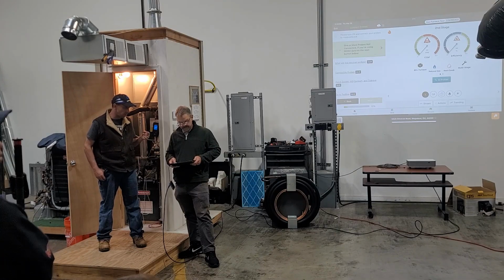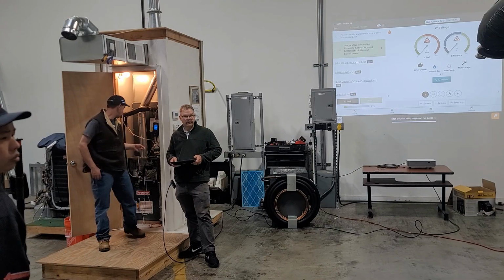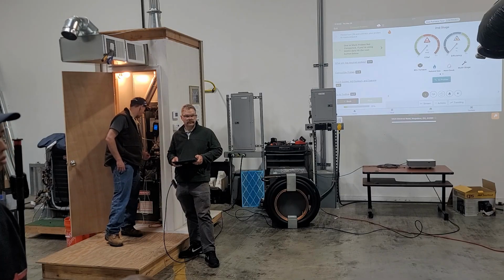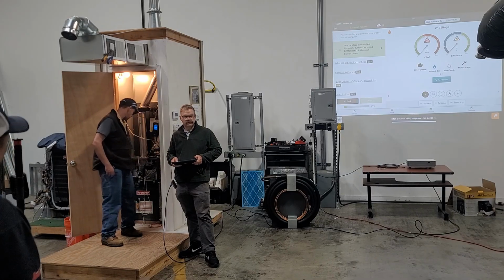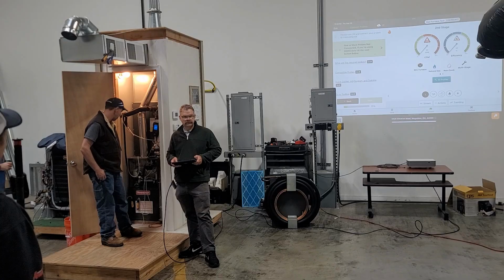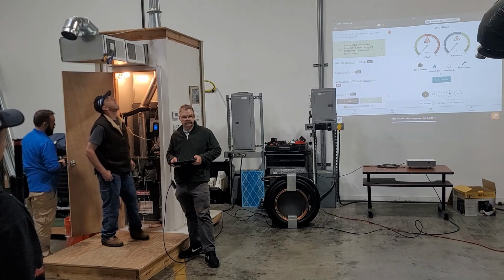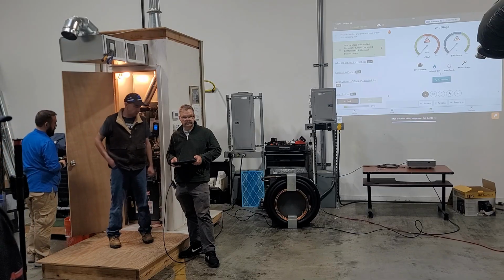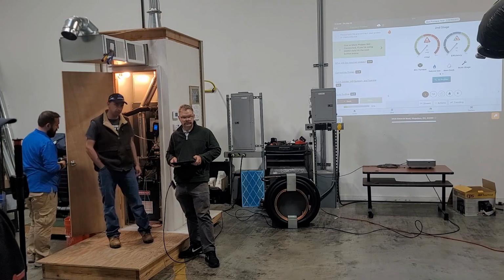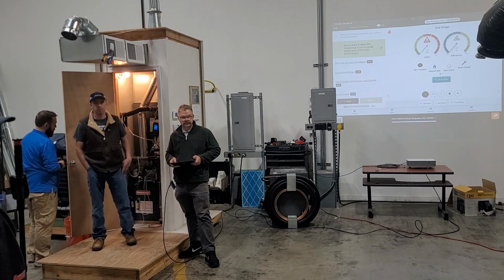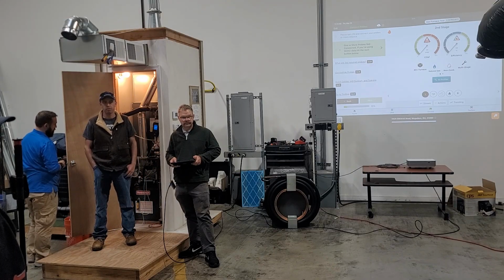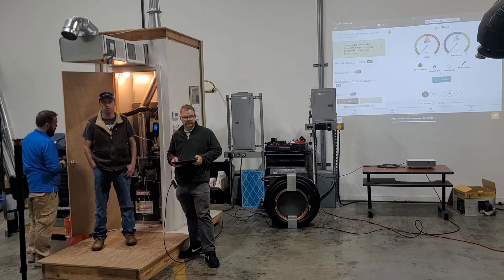For those of you who haven't done the gas workflow, I'd highly suggest it. I keep the Fieldpiece gauges, and I also have the Testo manometer, the dual manometer. My dual manometer does my airflow, my Fieldpiece does my supply and manifold pressures, and that way I can hook everything up while the system's off and never have to turn off the system to change my manometer.